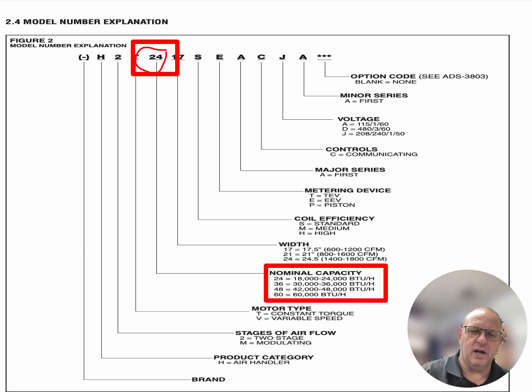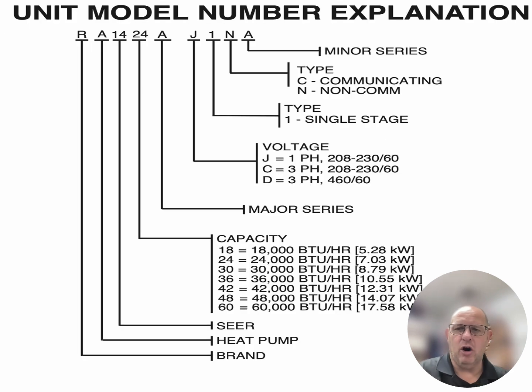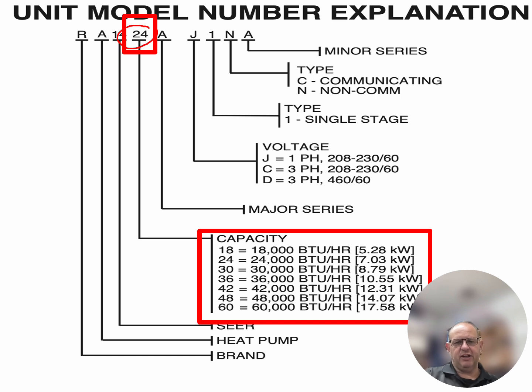Now we're going to swing across and look at a couple of different units that are out there. What do you think here? Unit model number explanation. We're looking at an RA14 24A J1NA. And just by looking at this, I can see a multiple of 12 right there, which happens to be the 24, and that 24 is going to tell me the capacity of that particular unit. And we see it as a 24,000 BTU capacity for the unit as we're looking at here. And this just happens to be, I do believe, a condensing unit that we're looking at.